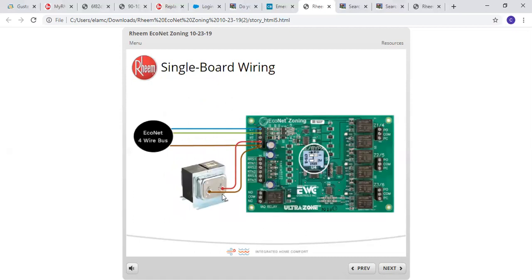So if you're going to use, in this case here, it's a single board. We're using more than 5 dampers, so we're going to add a secondary transformer right here. We're going to power this board up from here, our common and our R. But we're not going to bring the R in from our furnace board to this R, but we will bring our common in. So you'll have your 2 commons on common, and you'll use the additional secondary transformer to power your R.